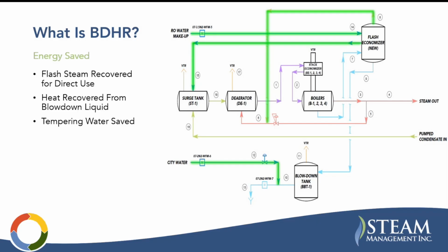Next, your makeup water is going to the unit and it's recovering heat. So you're getting some heat recovered out of that liquid. And then your last savings component, which is not insignificant, can often be 30% of your savings, is the tempering water that's saved from not having to temper that blowdown drain. It's reasonable for a blowdown heat recovery drain to come out at 100, 110 degrees. So you're well below your sewer limit, or you can be, and you pretty much eliminate the total requirement for tempering water, at least for surface blowdown.